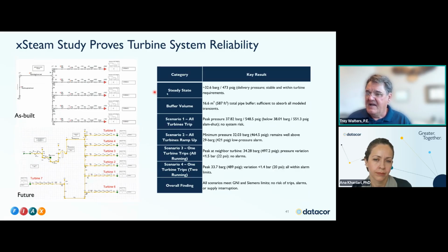They had different pressures and volumes that they wanted to meet. Overall findings, all scenarios met. This GNI, I think that's the local gas utility there in Ireland, the Irish gas utility, and the Siemens limits. They had no risks of trips, alarms, or supply interruption for the 5 and 7 turbine configurations. So they were happy with that. They could go forward confidently with construction.